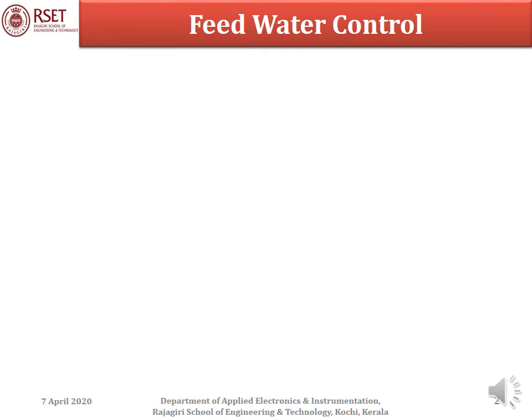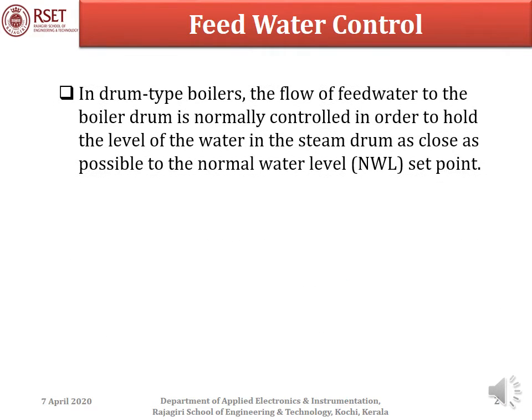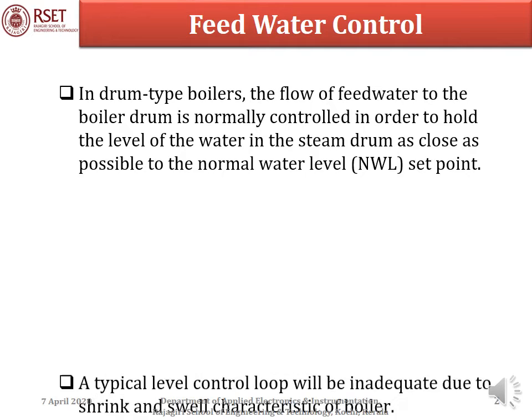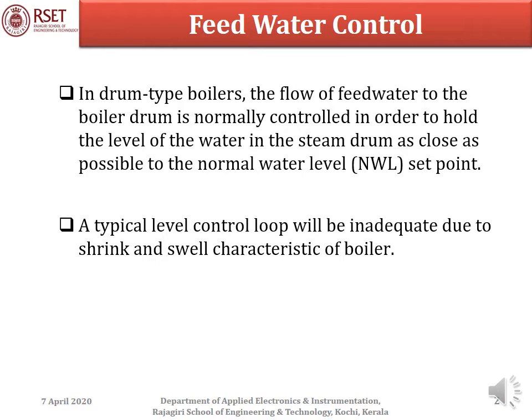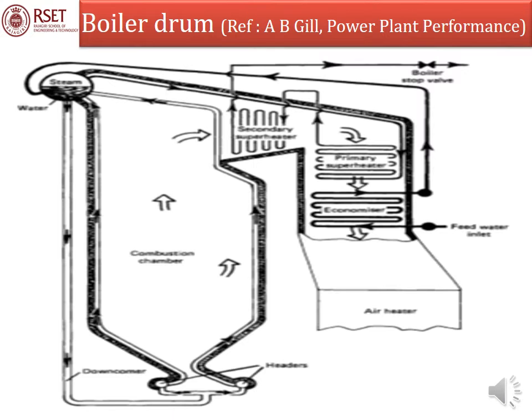Feed water control. In drum type boilers, the flow of feed water to the boiler drum is normally controlled in order to hold the level of water in the steam drum as close as possible to the normal water level set point. A typical level control loop will be inadequate due to the shrink and swell characteristics of boilers.